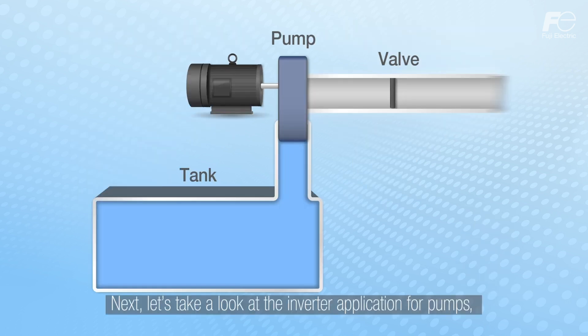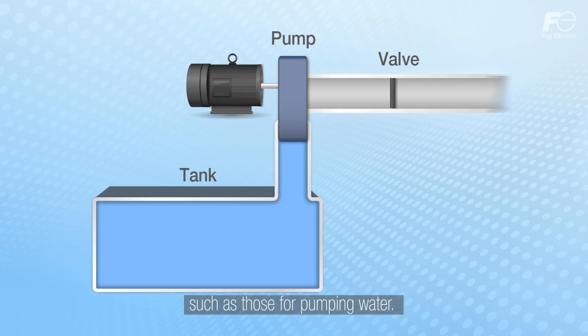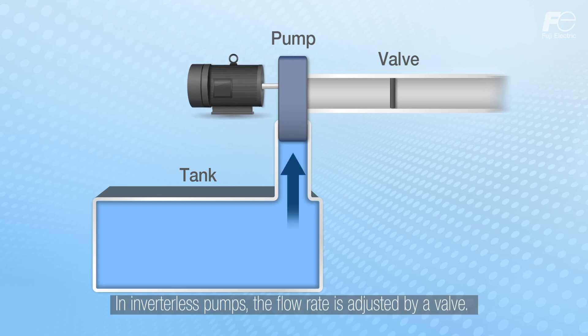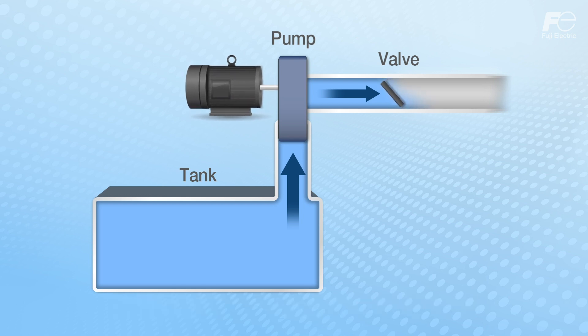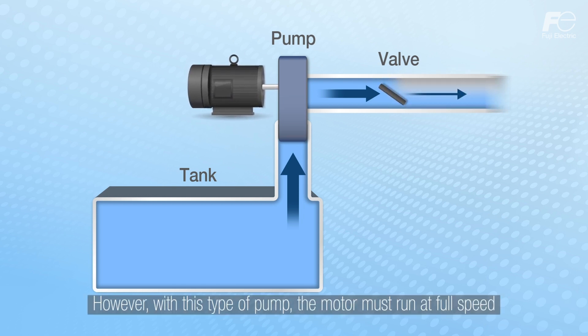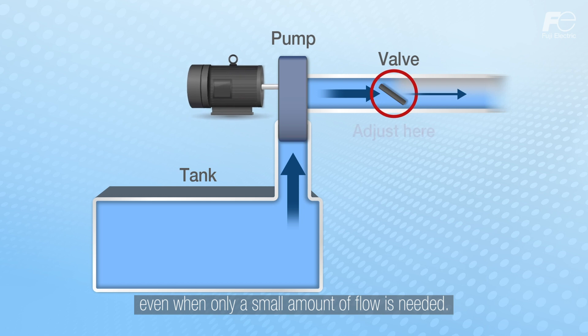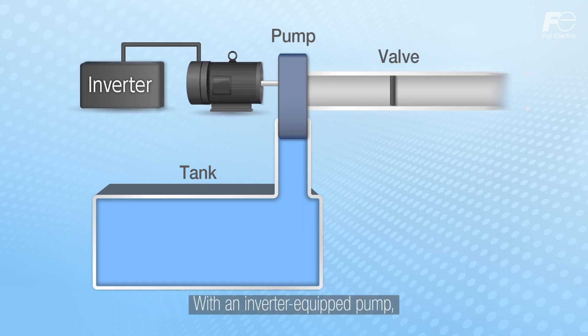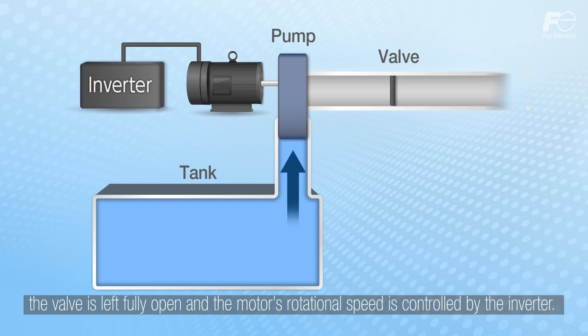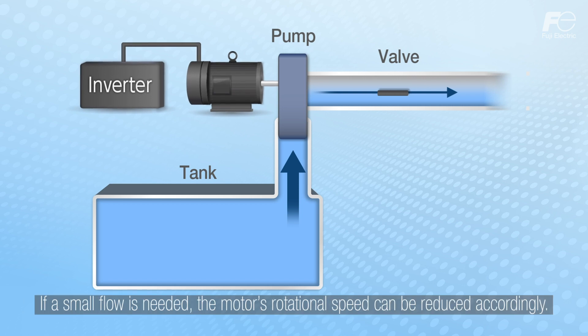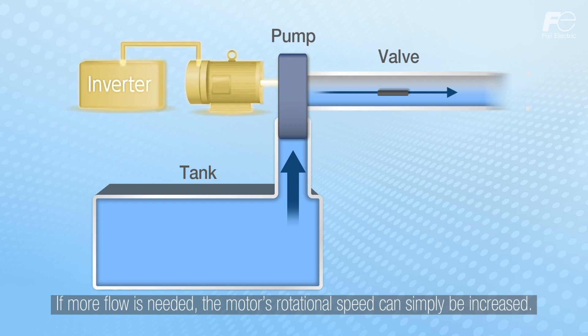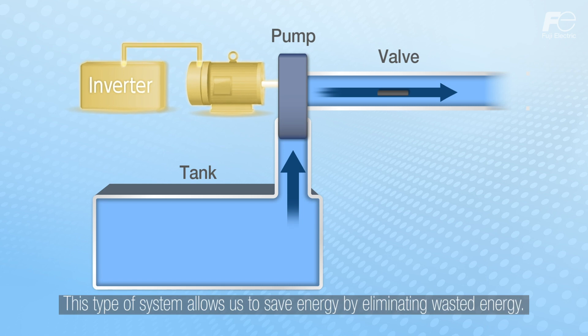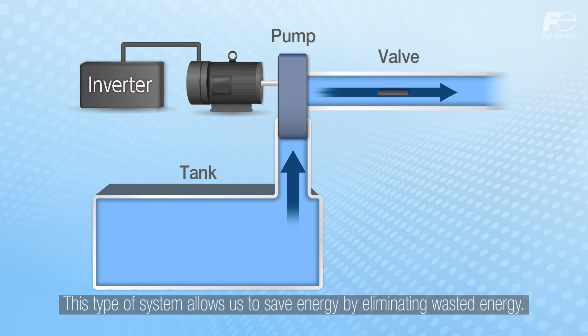Next, let's take a look at the inverter application for pumps such as those for pumping water. In inverterless pumps the flow rate is adjusted by a valve; however, the motor must run at full speed even when only a small amount of flow is needed. With an inverter-equipped pump, the valve is left fully open and the motor's rotational speed is controlled by the inverter. If a small flow is needed the motor's rotational speed can be reduced accordingly, and if more flow is needed the rotational speed can simply be increased. This type of system allows us to save energy by eliminating wasted energy.